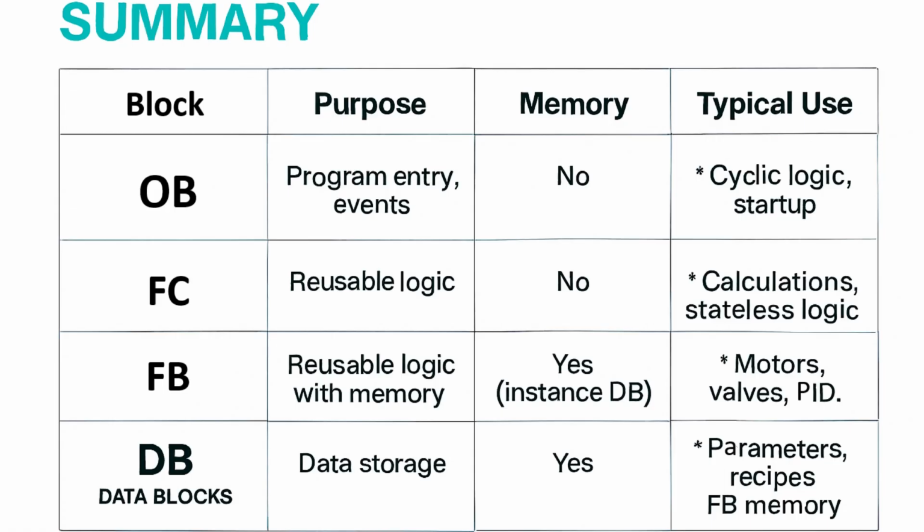Then we have FBs, function blocks. These are similar to FCs but with memory. Each FB uses an instance data block to store its internal state. Ideal for controlling motors, valves, PID loops, or any sequence logic.